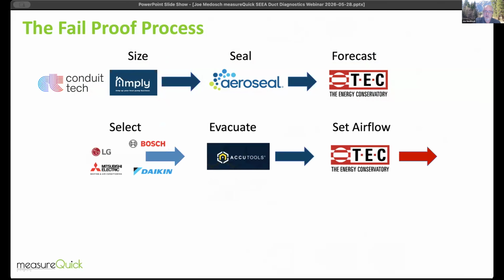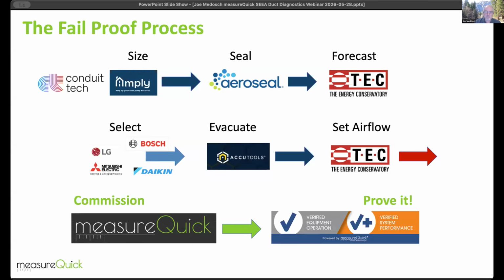All right. Next we're selecting our equipment. We evacuate with the AccuTools or a similar system, and we set the airflow again with the TrueFlow grid, right? And when you're done, you can commission with MeasureQuick and even prove it with more of an ACCA Manual J process. So these are the fundamental methods that are out there. Unfortunately, so many people are not following through with some of these additional tests to confirm. If you don't test, you're guessing. That's a common theme that's been out there for quite a long time.